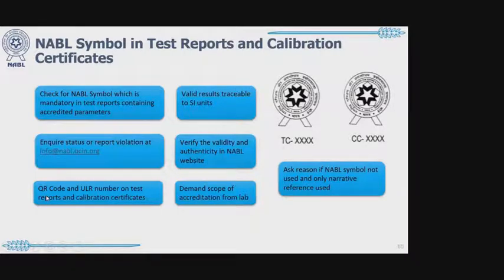One very important thing is the QR code and ULR number system on test reports and calibration certificates, which we have told the laboratories to implement. The ULR code is a requirement of GeM, the Government e-Marketplace. For uploading any product, the seller has to upload a test report or calibration certificate from a NABL accredited laboratory, which has to bear a unique laboratory report number, the ULR number. This is an 18-digit code, uniquely given to each test report or calibration certificate generated by that laboratory. So if GeM needs to cross-check with the laboratory, it can do it using the ULR number.